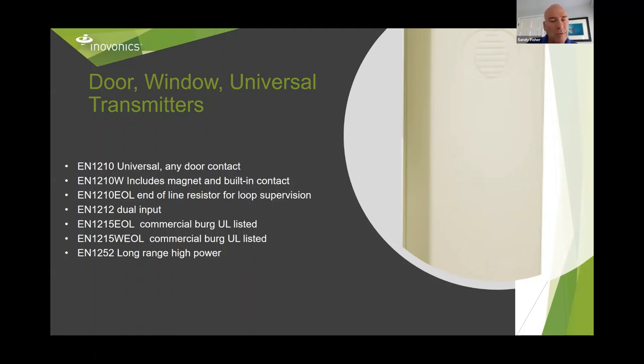In general, wireless range or distance in building and through building, I'd say is a couple hundred feet in a challenging RF environment. And then every repeater you add gives you another hop. And again, up to 10 hops, that should be enough to cover any large, massive commercial or industrial premise. And again, the high power is roughly twice that distance.